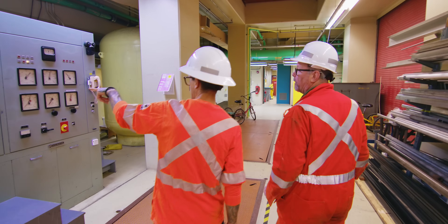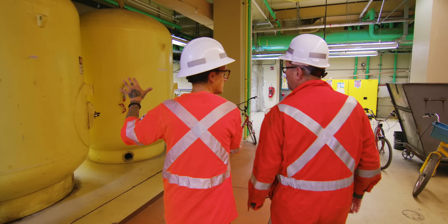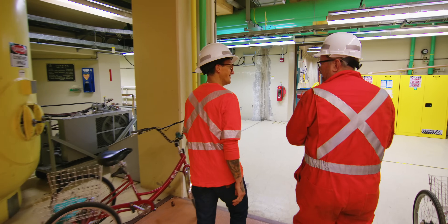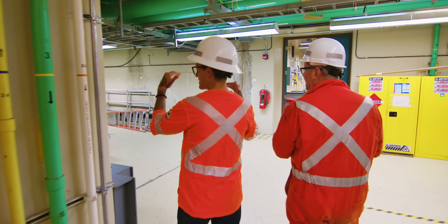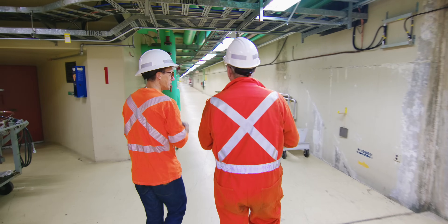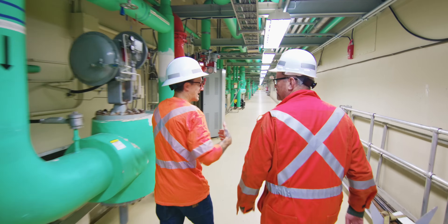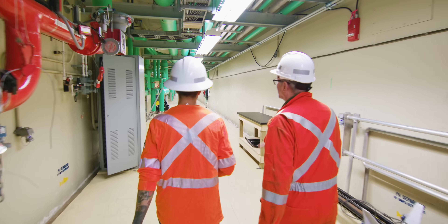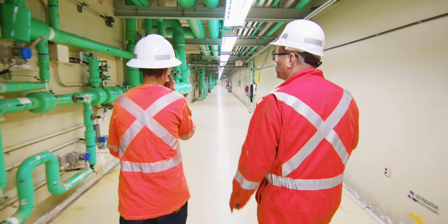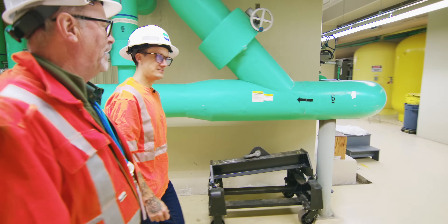Robert, these are the governors I was talking about — they're big hydraulic. So this is hydraulic fluid, and these are accumulator tanks maintaining that pressure. As we go into the unit, we'll be able to look into one of the turbine pits and see the massive wicket gate arms that the governors control. That's controlling the amount of water flowing into the units. So can you actually turn them up and down to generate less or more? That's right.